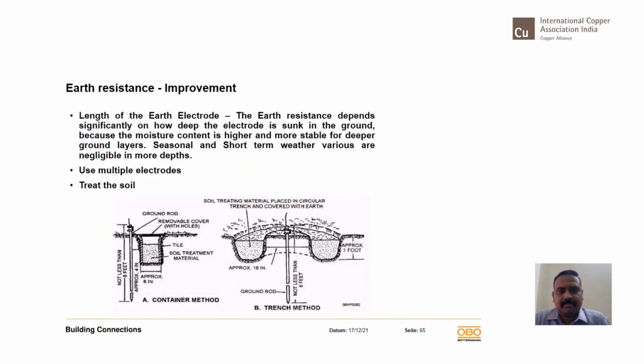Now, the old conventional method of CI pipe or GI pipe being used is clearly illustrated in the IEEE standard, which says if you are using that kind of pipe and using salt and charcoal, you should not put the salt and charcoal along with the electrode. The standard says you have to dig a trench around the electrode and put the salt and charcoal there. Only the electrolytes of the salt and charcoal have to go to the electrode and not the salt and charcoal directly. So if you do it directly, obviously there are going to be damages to the electrode, the longevity will not be there, and your resistance cannot be consistent over a period of time.